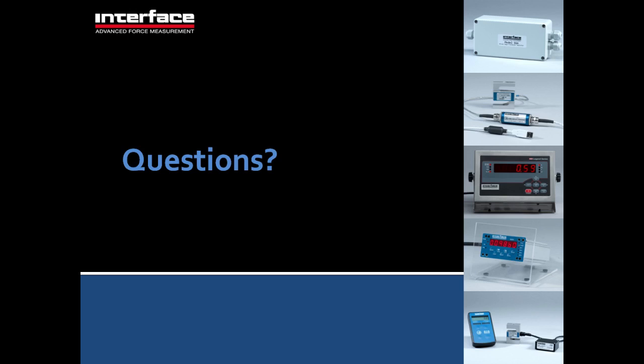Good question. We actually do see a fair number of instruments come back for calibration, but typically they're attached to a load cell when they come back. We don't see very many instruments come back by themselves for calibration. There's a couple of reasons for that. One would be that many instruments aren't really capable of being calibrated. A signal conditioner or your basic digital indicator basically takes a signal and converts it to a displayed value. So it doesn't really have any internal calibration available.